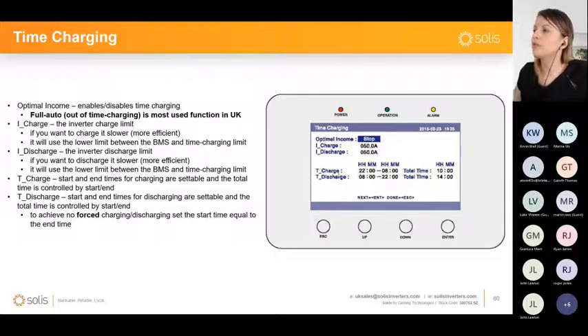And for example, you have a charging time during nighttime, but you don't want the battery to be forcibly discharged. You just want to let it be discharged in self-use mode when there is consumption that is not being covered by the PV. Then for time discharging, you can just zero it out. So set it to 0000, so it will show total discharge time of 0 hours, and this will not be applied.